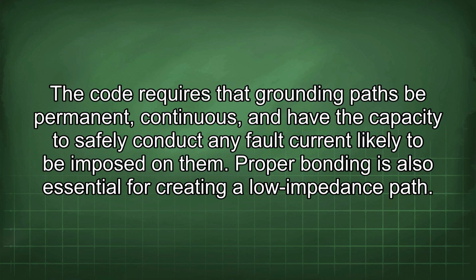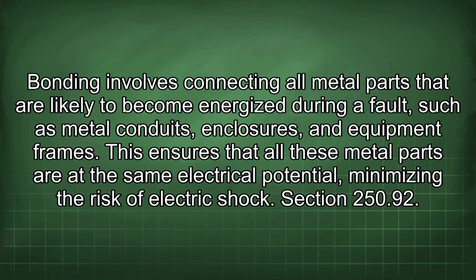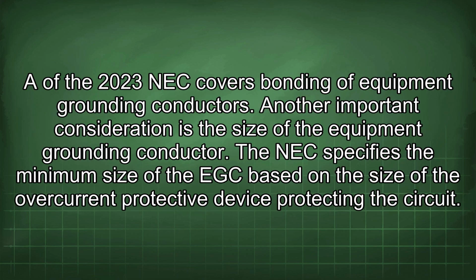Proper bonding is also essential for creating a low impedance path. Bonding involves connecting all metal parts that are likely to become energized during a fault, such as metal conduits, enclosures, and equipment frames. This ensures that all these metal parts are at the same electrical potential, minimizing the risk of electric shock. Section 250.92 of the 2023 NEC covers bonding of equipment grounding conductors.